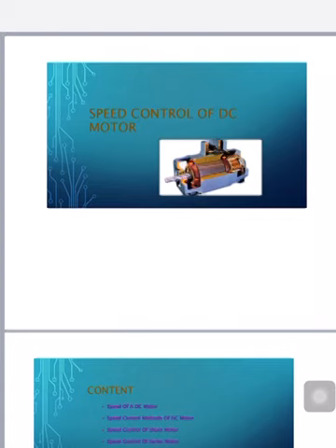So DC motors generally consist of rotor mounted windings, the armature, and stator windings, the field poles. In all DC motors except permanent magnet brushless motors, current must be conducted to the armature windings by passing current through carbon brushes that slide over a set of copper surfaces called a commutator, which is mounted on the rotor. And the commutator bars are soldered to armature coils.